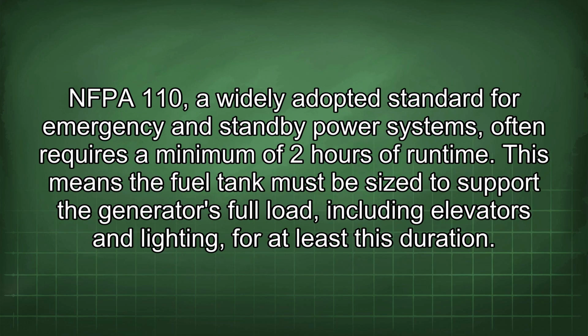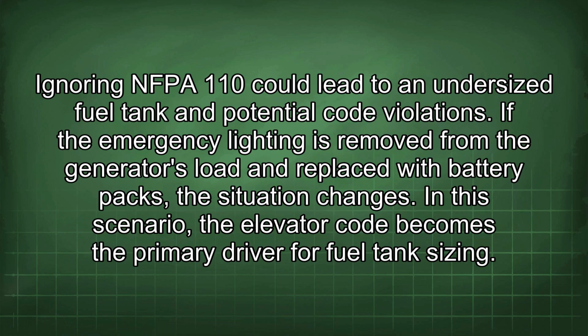NFPA 110, a widely adopted standard for emergency and standby power systems, often requires a minimum of 2 hours of runtime. This means the fuel tank must be sized to support the generator's full load, including elevators and lighting, for at least this duration. Ignoring NFPA 110 could lead to an undersized fuel tank and potential code violations.